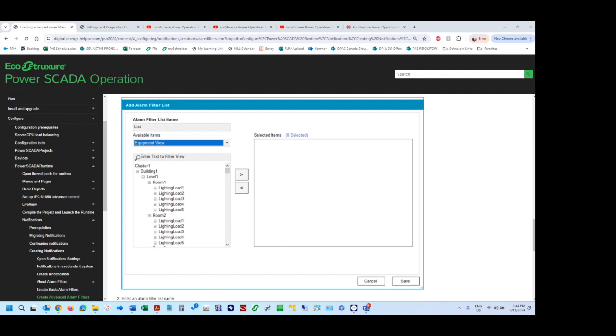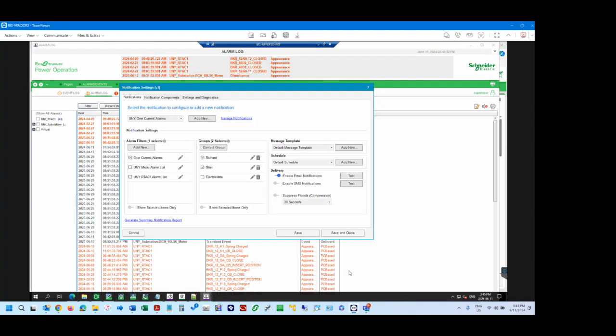Yeah, so I have to check into that, whether EPO has to look at specific set points that it's already preset to look at. Because I know that it already knows certain alarms coming from the meters. Maybe we have to repurpose one of them, or if we make a new one, we might have to make a change to the mapping to allow it. So I have to check into that. Because at the end of the day, it's going to find that alarm, because it does have the ability to see those onboard alarms and then pull them.